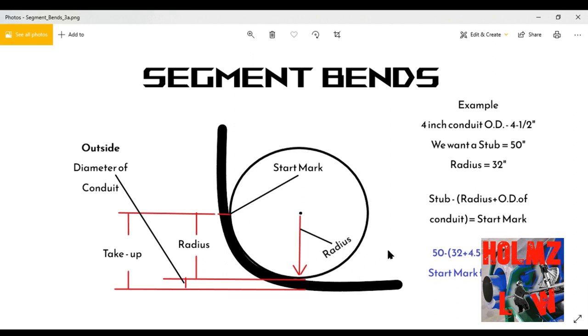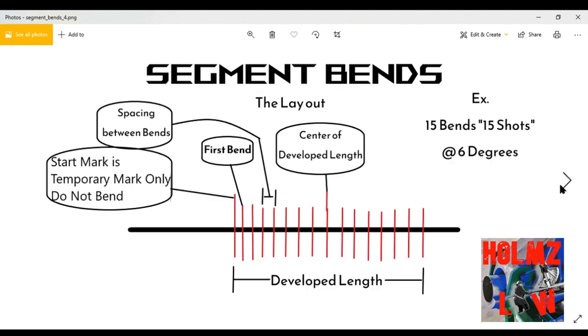This is an example using a radius from the inside edge: you would use the radius plus the whole outside diameter of the conduit, then subtract from the stub. So it matters whether you're using a centerline radius or an inside radius — that determines which formula you use.